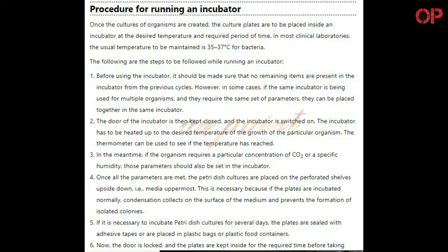Step 3: The incubator has to be heated up to the desired temperature for the growth of the particular organism. The thermometer can be used to see if the temperature has been reached. If the organism requires a particular concentration of CO2 or a specific humidity, those parameters should also be set in the incubator. Step 4: Once all the parameters are met, the petri dish cultures are placed on the perforated shelves upside-down, that is, media uppermost. This is necessary because if the plates are incubated normally, condensation collects on the surface of the medium and prevents the formation of isolated colonies.